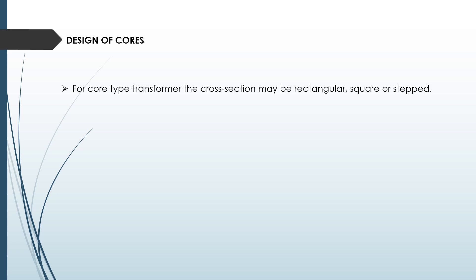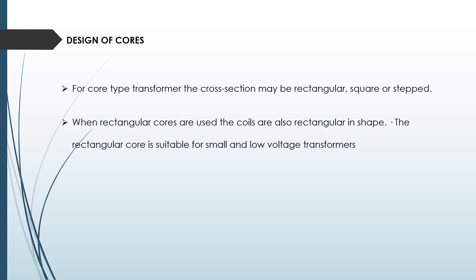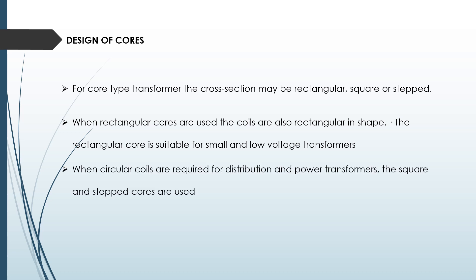Next is design of core. For transformer core, the cross section may be rectangular type, square type, or step type. We will discuss these one by one. When rectangular cores are used, the coils are also rectangular in shape. The rectangular core is suitable for small and low voltage transformers. When circular coils are required for distribution and power transformers, square cores and step cores are used.